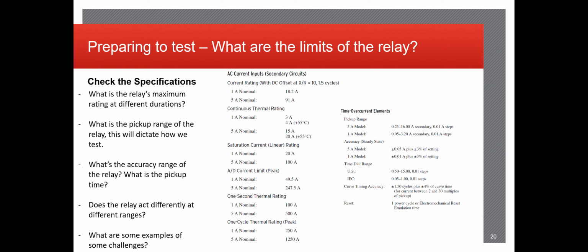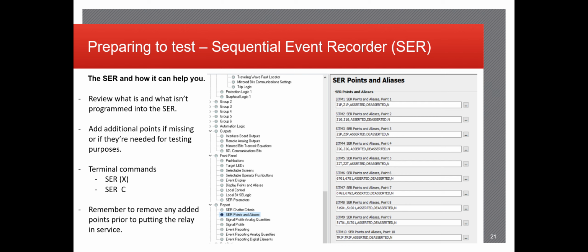Some examples of challenges. Again, we talked about not setting that spare output to the element you want to pick up, not putting in your test leads in the correct portions of the relays, stuff like that. Prepping your SER. You always want to save a copy of the SER and then clear it. Clearing the SER ensures that when you run your test, the only thing that's going to show up on the SER is everything that's occurring during the test, meaning it'll see whatever relay elements pick up, outputs that may get triggered or operated, etc., etc.